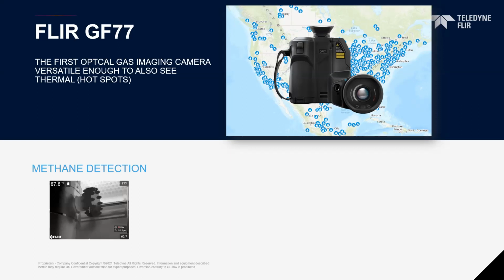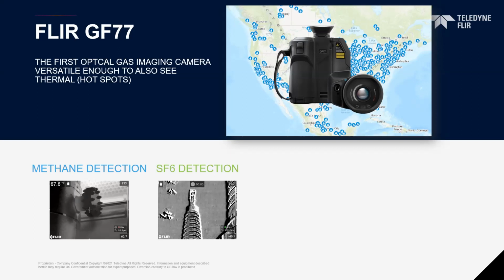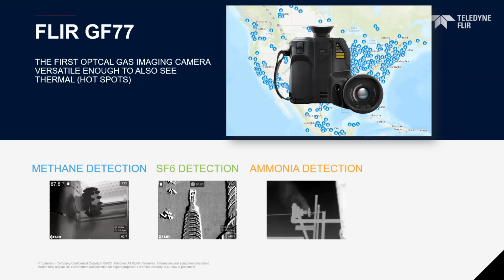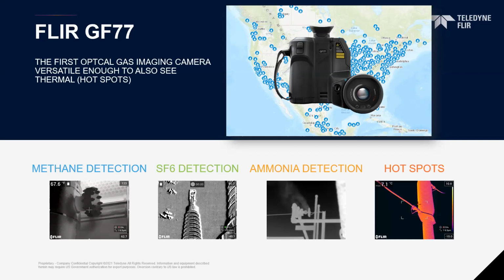It can detect methane gas. It can detect SF6 leaks from circuit breakers near the generation plant. Even plants with combined cycle that use ammonia—this camera can pick up ammonia leaks and detect where those are coming from. On top of those three main gases, and some additional gases, it can also be used as a thermal imaging camera detecting hot spots, so you can do your predictive and preventative maintenance with thermal imaging as well. It's really a jack-of-all-trades camera that packs a ton of value.